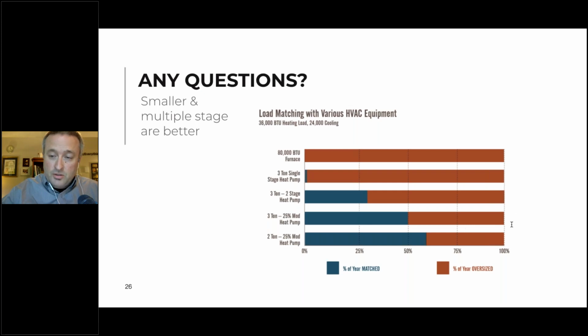And there, Michael Collins, is it critical to always run a blower door test to calculate load? Well, that depends. Do you want it to be right or not? If you don't want it to be right, don't do it. Without a blower door, we find that load calcs are easily plus or minus 30,000 BTUs. And keep in mind, we're finding loads consistently in Cleveland for 2,000 square foot homes and under. This is a cold climate that are under 3 tons. So you are plus or minus a piece of equipment without a blower door.